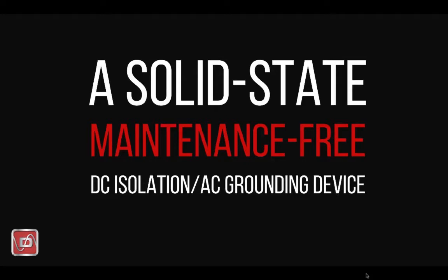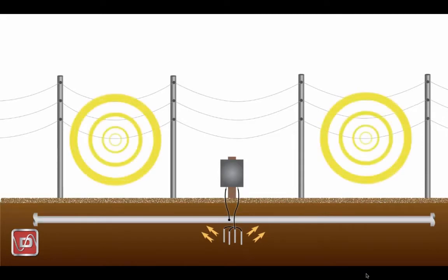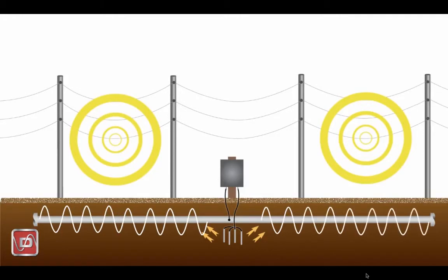Okay, moving on. Let's look at a normal AC mitigation application and discuss quickly why you should use one of these devices. Let's start with a simple pipeline with a rectifier on it. The rectifier is used to put CP current on the pipeline, providing a critical piece of your cathodic protection plans. It's pretty important that we maintain our CP system at adequate levels. Many pipelines are located in rights-of-way with overhead power lines, creating induced AC voltage effects. This is where our AC mitigation projects come in.